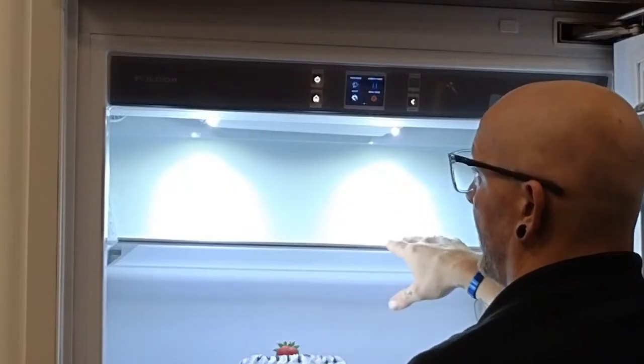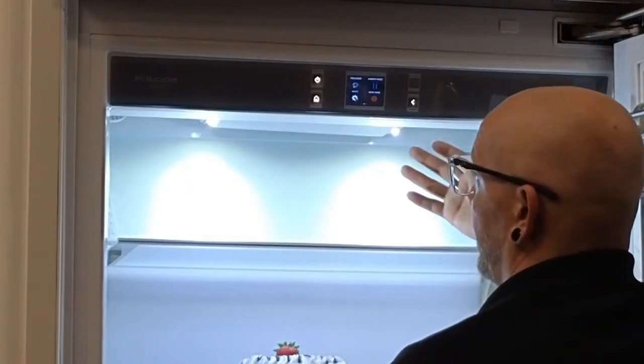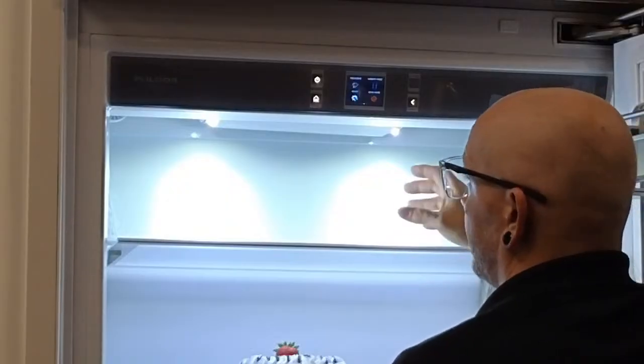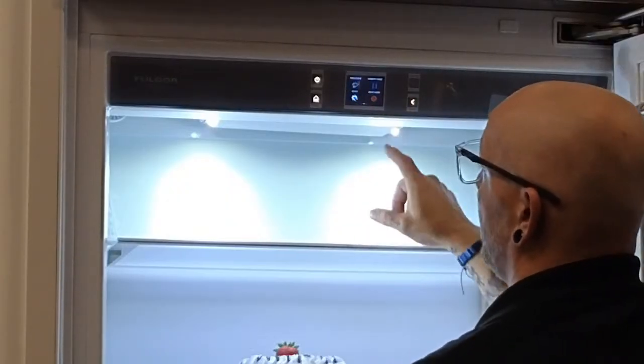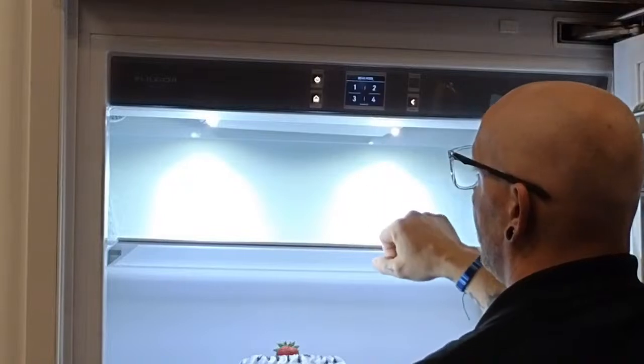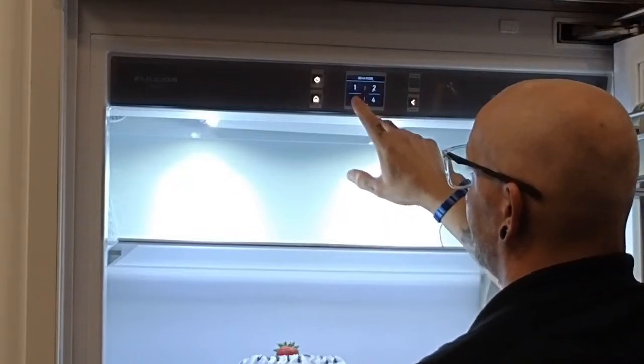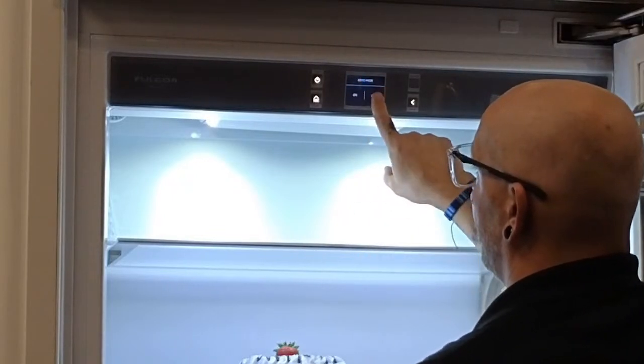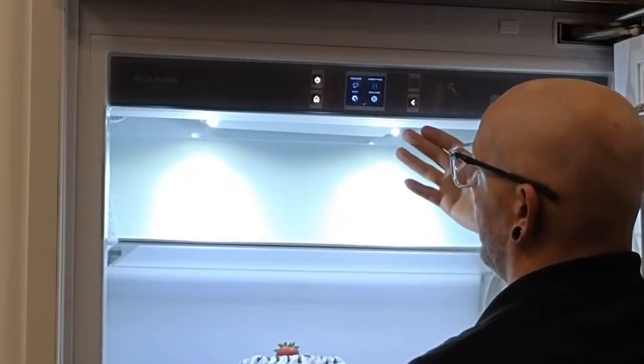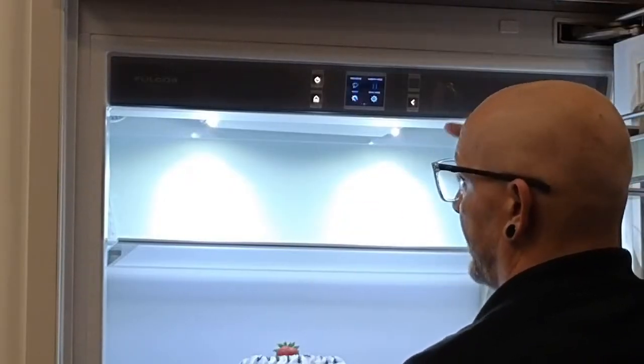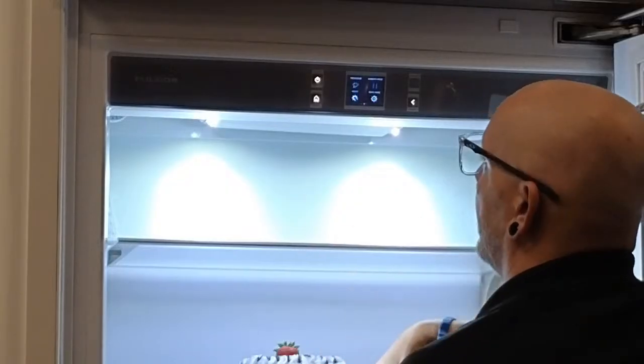Sometimes units get sold off of a showroom floor, they may still be in demo mode. Customer calls and says it's not cooling. May just be able to scroll over to demo mode to see if it's illuminated. If it is, push it. Super secret code. We're going to turn demo mode off. Now it's not illuminated anymore. You'll hear the compressors kick on, the fans kick on, and everything ramp back up.